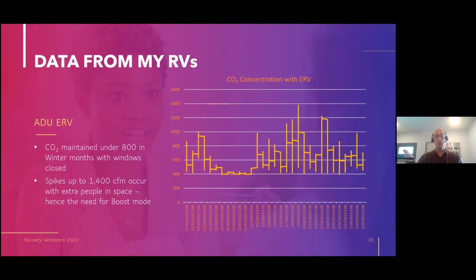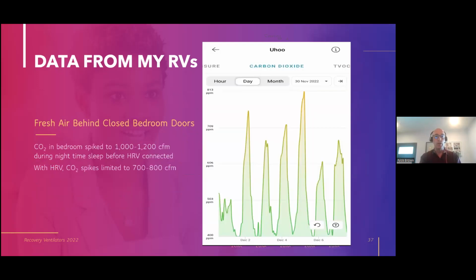But there are spikes up to 1400 on one day, 1200, 1000 on other days. Probably they've got the windows closed, they've got extra people over. This shows the need for boost mode or opening your windows. And that's when you see the line drop like a stone, that's when they open the windows. So I thought that was really interesting to see too, that this ERV really is doing a nice job, even in winter when the windows are closed generally, of maintaining indoor air quality.